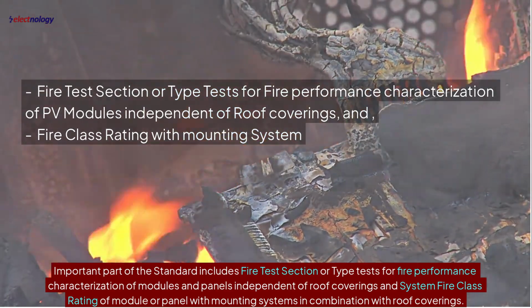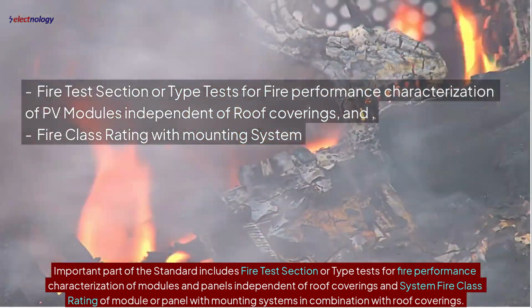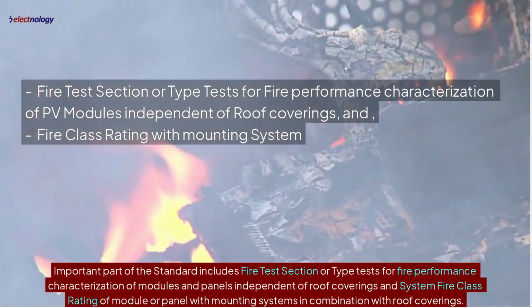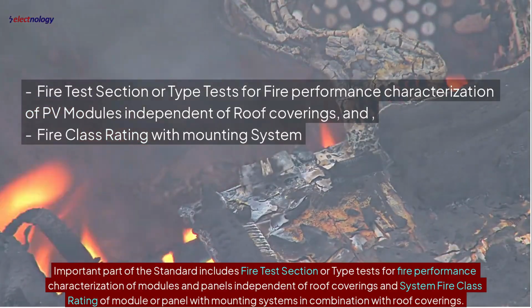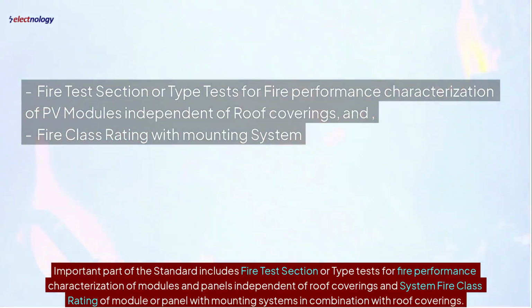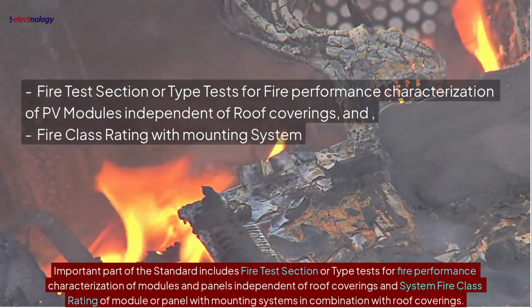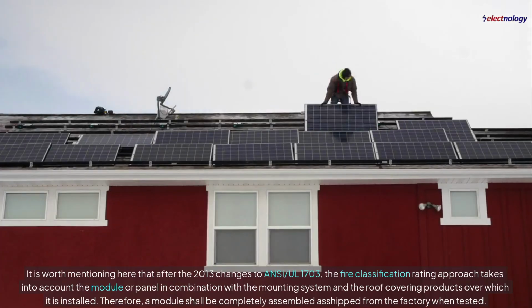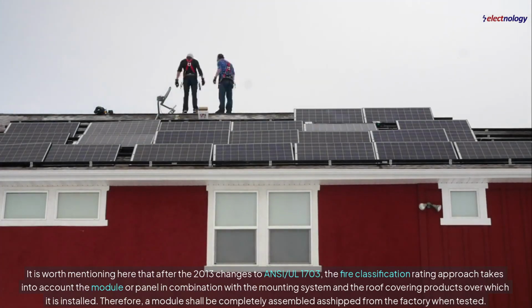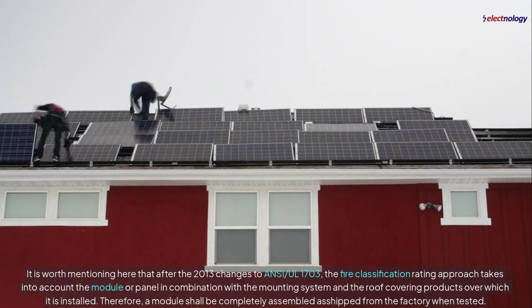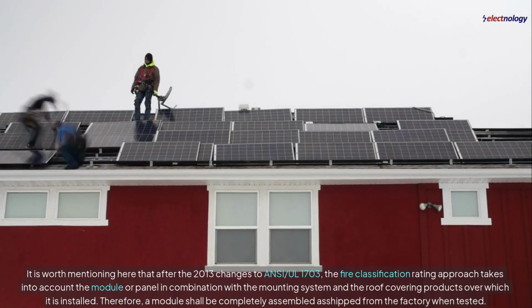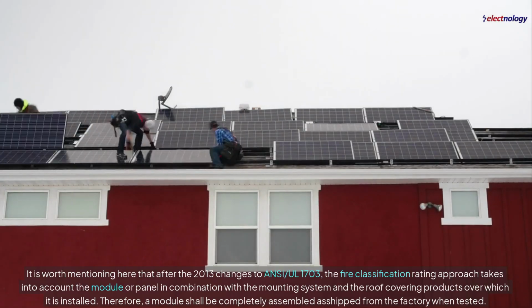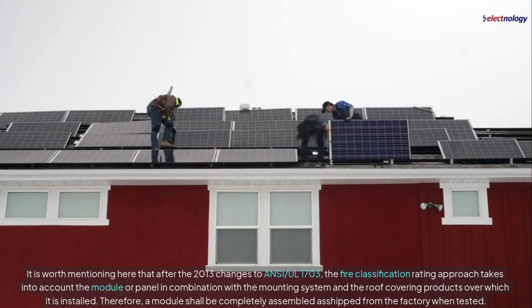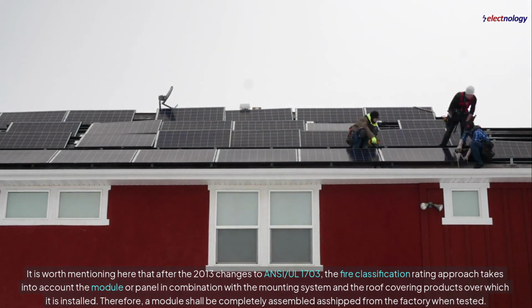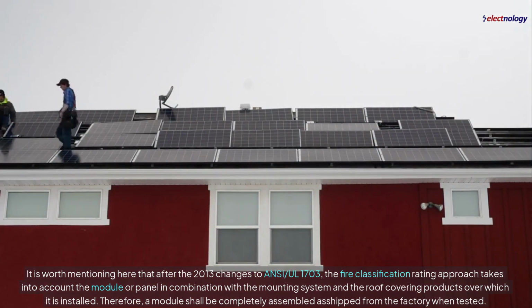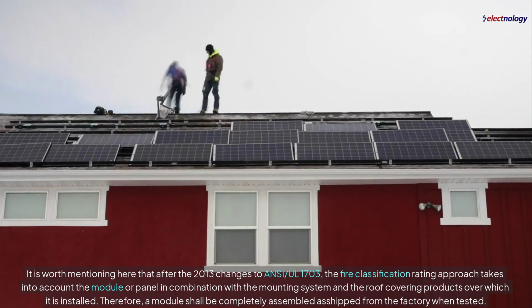An important part of the standard includes the fire test section, or type tests, for fire performance characterization of modules and panels independent of roof coverings, and system fire class rating of module or panel with mounting systems in combination with roof coverings. It is worth mentioning here that after the 2013 changes to ANSI UL 1703, the fire classification rating approach takes into account the module or panel in combination with the mounting system and the roof covering products over which it is installed. Therefore, a module shall be completely assembled as shipped from the factory when tested.